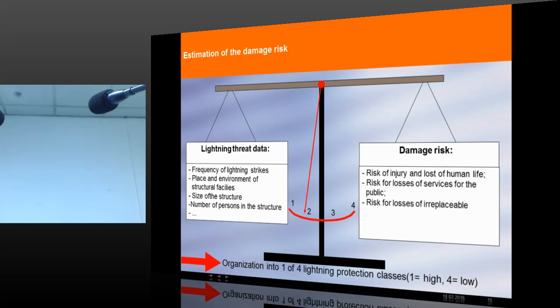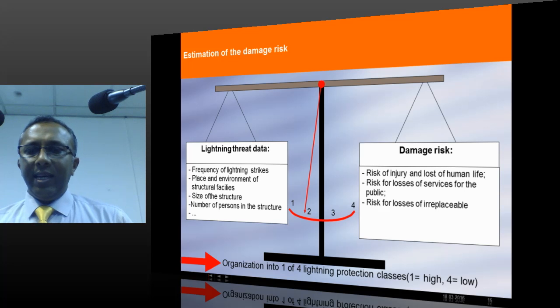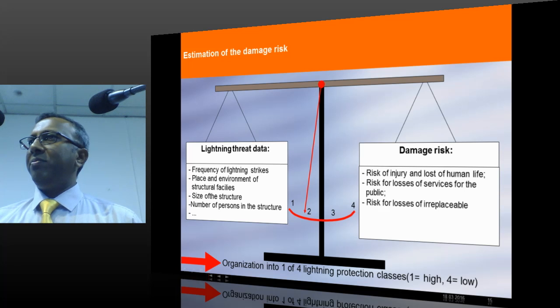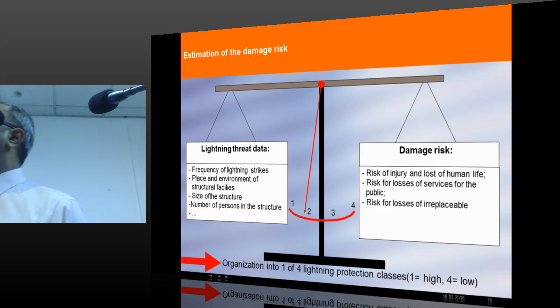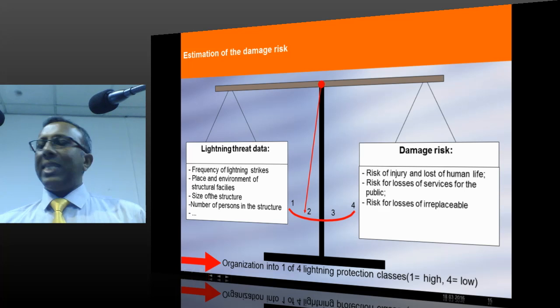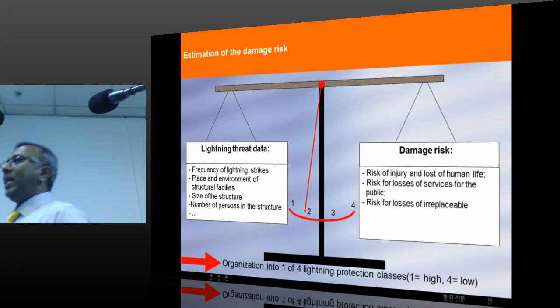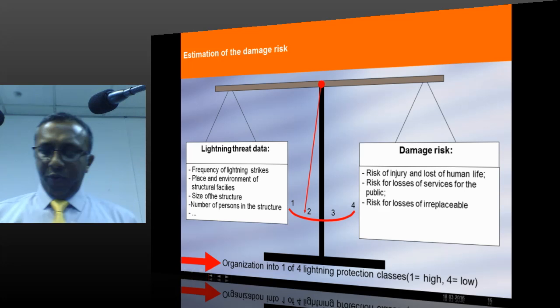Depending upon the frequency of lightning, place and environment of the structure, size of the structure, number of people inside the structure, and finally the risk of injury and loss of human life. That means in case of a direct strike, a fire may happen, and in case of fire, the size of the building and the people inside the building are important. So what kind of risk is associated is also studied in the standard very well. Based on the risk as well as the protection required, the standard says you can divide lightning protection into 4 levels. 1 is the highest and 4 is the lowest. Lightning protection level 1 to 4.